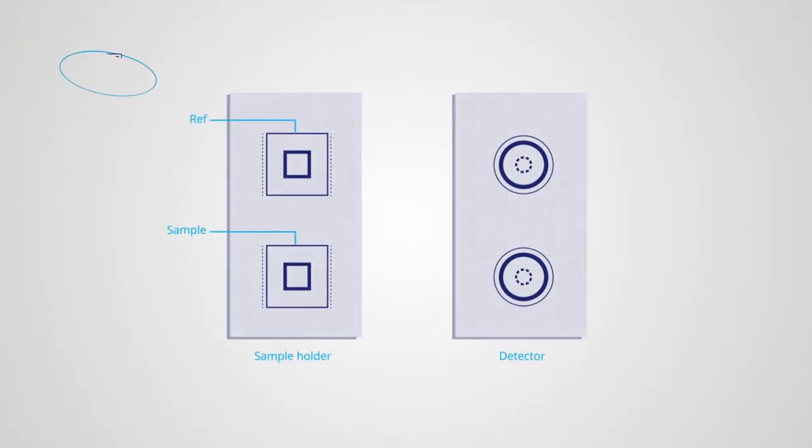If reflected, the light beam travels through the reference cell. On the other hand, if the light beam is transmitted, it travels through the sample cell.